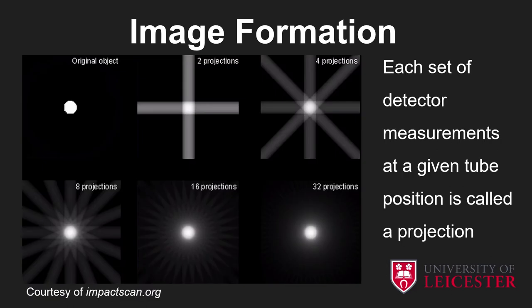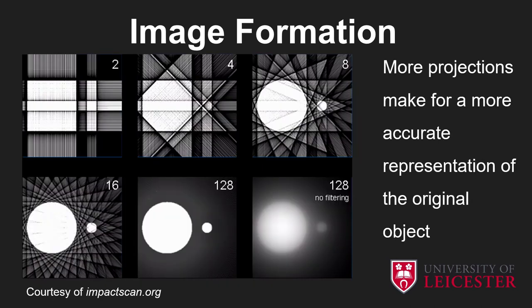We don't just take one picture of the object we're scanning — we take several, each called a projection. You can see from this sequence of pictures that the more projections we take, the more exposures we make of the tube moving around the patient, the better the picture is in approximating what the original object was — in this case a sphere floating in space. With a slightly more complicated object, the more projections you have the more true the image is. There's also more processing involved in sharpening and fine-tuning that image.